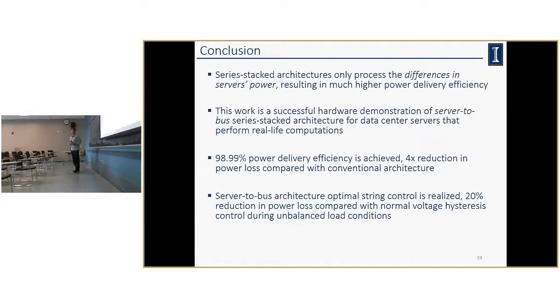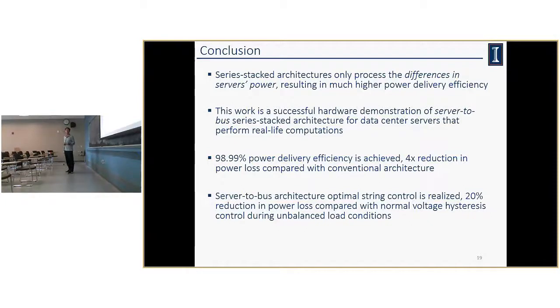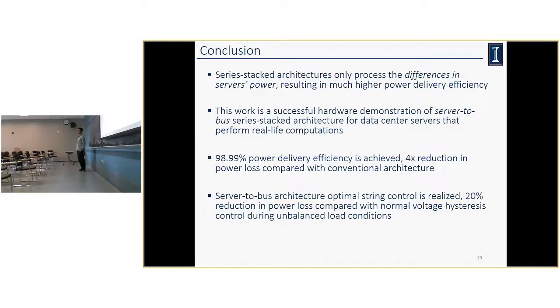In conclusion, the series stack architecture, since it only processes the difference in server power, can achieve much higher power delivery efficiency than conventional architecture. This work is a successful hardware demonstration of the server-to-bus series stack architecture for data center servers performing real-life computation. A power delivery efficiency of 98.99% is achieved — a four times reduction in power loss compared to conventional architecture. The optimal string current control achieves a 20% reduction in power loss compared to voltage hysteresis control during unbalanced load scenarios. Thank you.